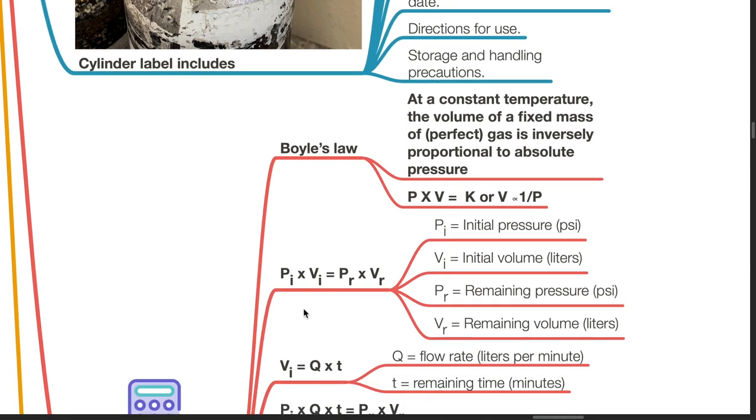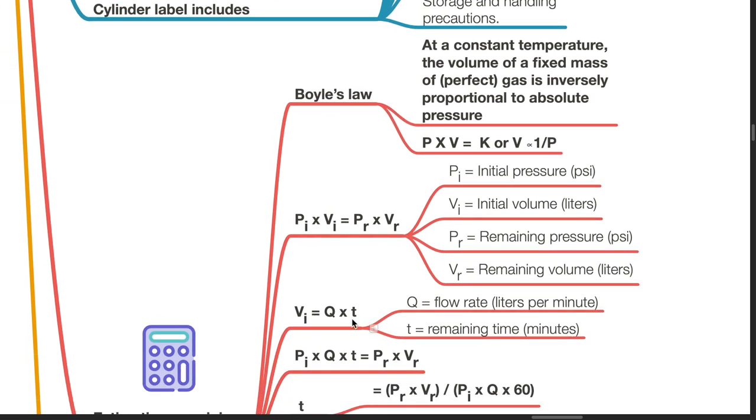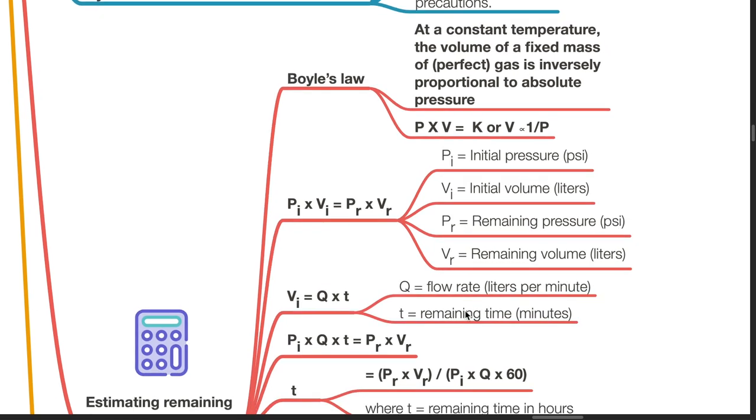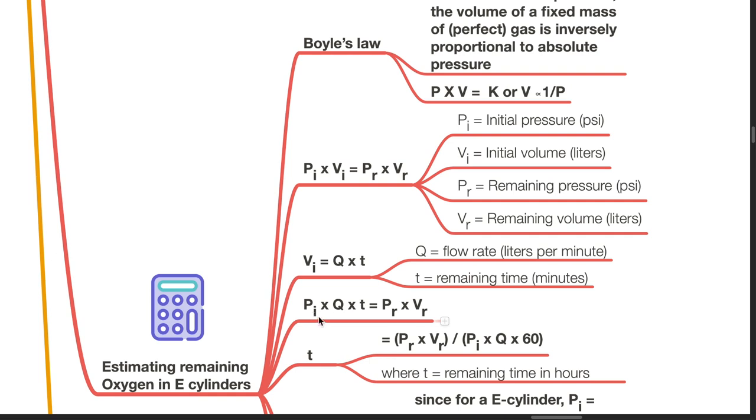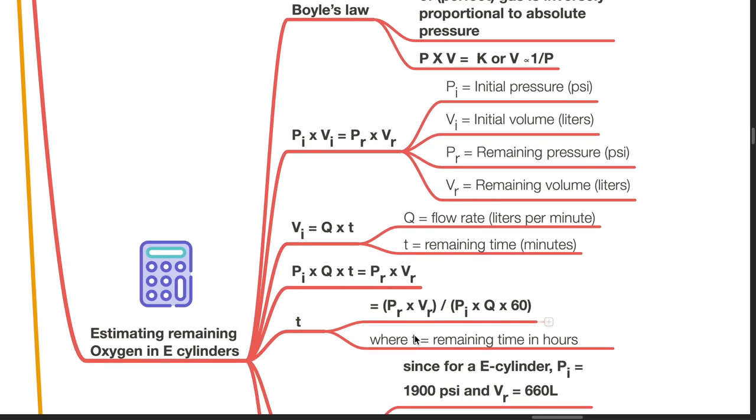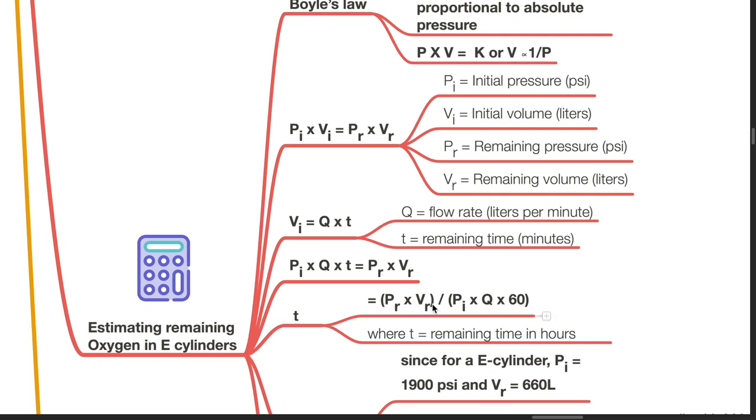PI times VI equals PR times VR, where PI equals the initial pressure, VI equals the initial volume in litres, PR equals the remaining pressure in PSI, and VR equals the remaining volume in litres. VI equals Q times T, where Q equals flow rate in litres per minute, and T equals remaining time in minutes. PI times Q times T equals PR times VR. T equals PR times VR divided by PI times Q times 60.